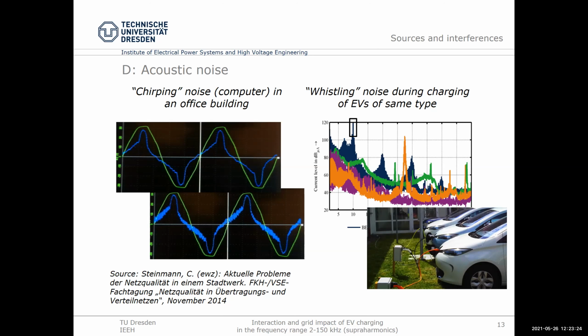Another very interesting issue that came up recently is the so-called chirping noise, or beating. This mainly happens with multiple devices of the same make, which have virtually the same switching frequency, but due to manufacturing tolerances are not exactly the same. So imagine you have 10 kilohertz and 10,001 hertz - due to the difference, you get a beating of 1 hertz.